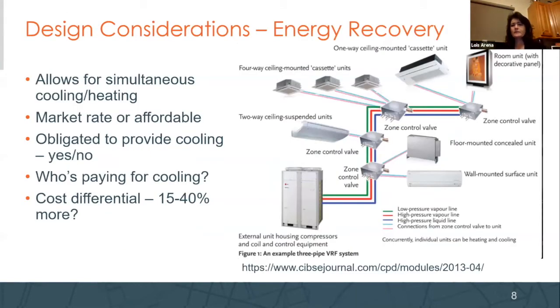So again, this is a heat recovery system. We have 3 refrigerant loops running through the building. That extra loop is so that you can share the refrigerant and exchange heat from one apartment to the other. That's what makes it work, the simultaneous heating and cooling. That's what makes it more comfortable.